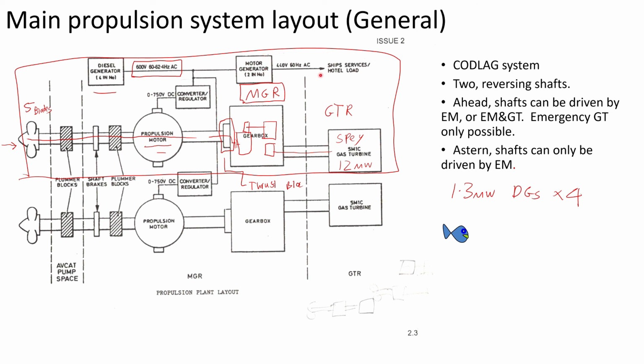Now, 60 hertz is not the UK standard frequency, which is in fact 50 hertz. However, the UK is a NATO country, therefore all NATO warships use 60 hertz as a standard frequency, so that we can all use each other's source supplies, portable generators, and so on. In order to achieve a very stable 60 Hz frequency, which is needed for things like the radars, etc., we are using 2 motor generators, and each one of them is 900 kilowatts. And those motor generators transfer the 600 volt 62 Hz into 440 volt 60 Hz.